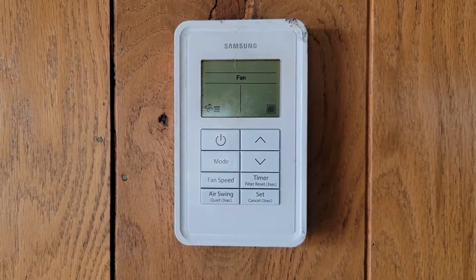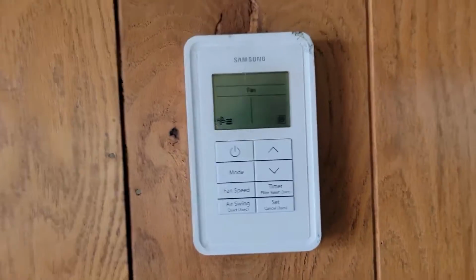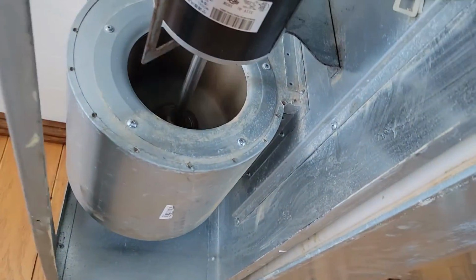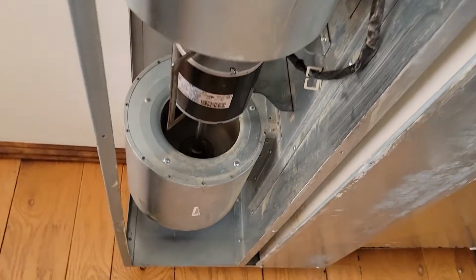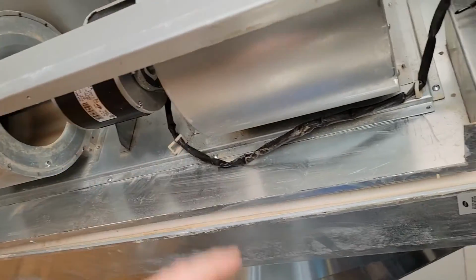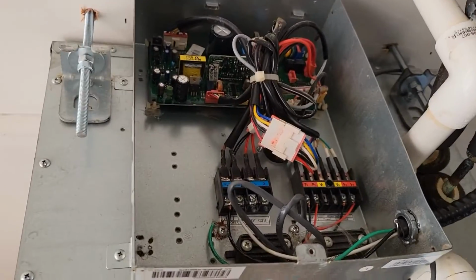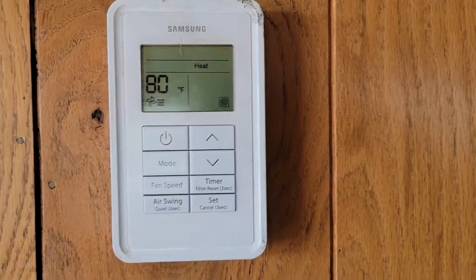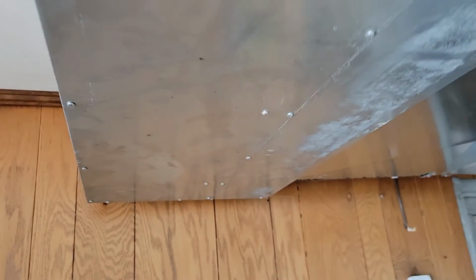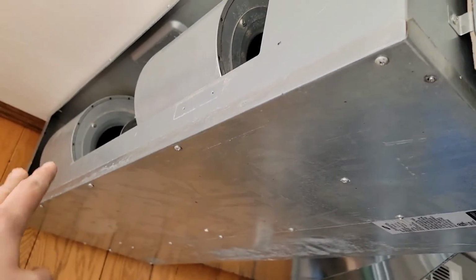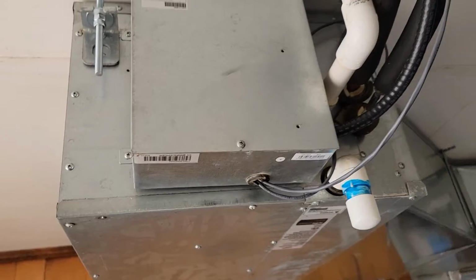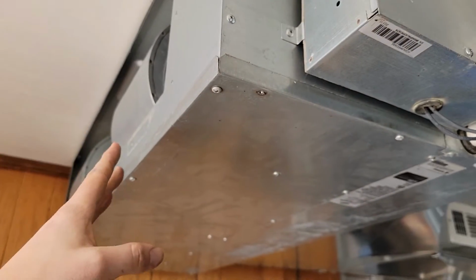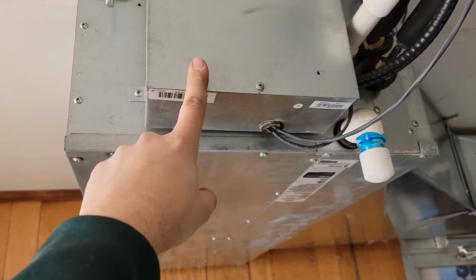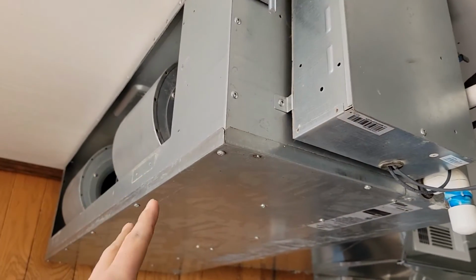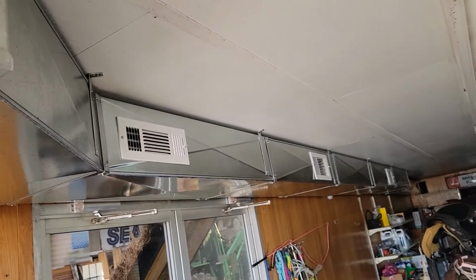So we restarted the equipment, and we've turned just the fan on, and it's on high speed. And now our motor is running properly. Sounds smooth. Let's put all the panels back together and turn this unit on heating. All right, now I'm going to test the heating. Got everything back together. Got to put the little brackets on for the filter. Notice the indoor fan's not on because in heating, the outdoor equipment comes on. And then once the evaporator sensors measure the coil temperature of 99 degrees, then the indoor comes on.